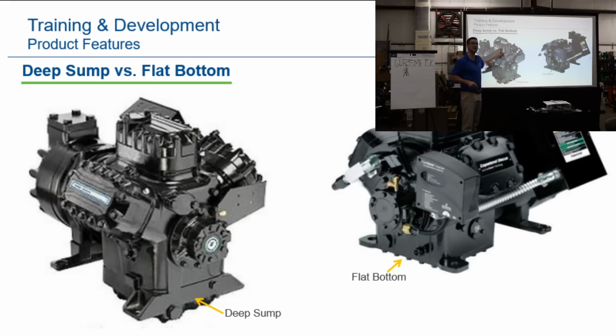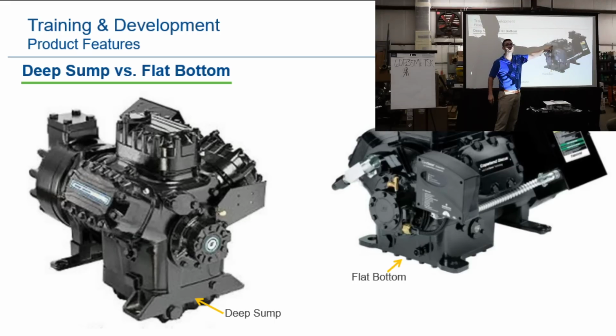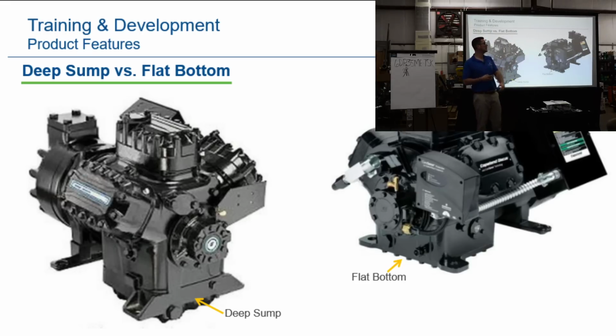D2 we call it. See, there's 15 bolts on the top of the head of this compressor. See this compressor here, same 6D compressor. Do you see how there's only 9 bolts on that? This is a D3. You can't switch this. So over the last 5, 6, 7 years, we've been selling OEMs this type of compressor called a D3, Discus 3. The replacement model you're going to get is this. And a lot of guys are like, no, I need the same compressor. Like I said, swapping like for like.